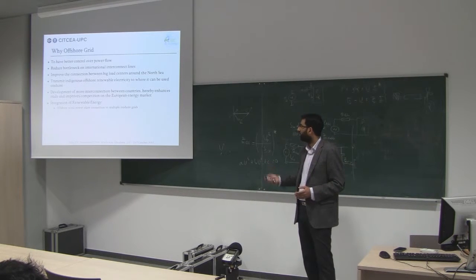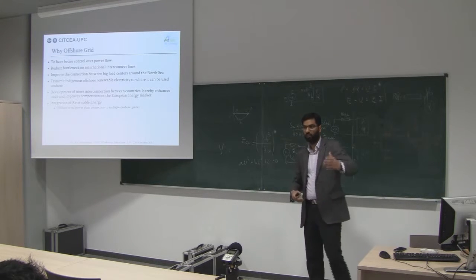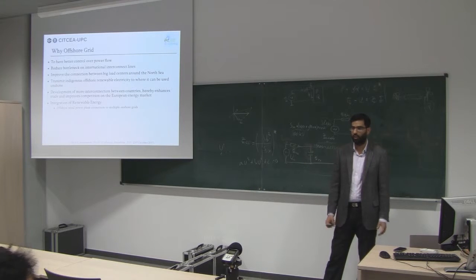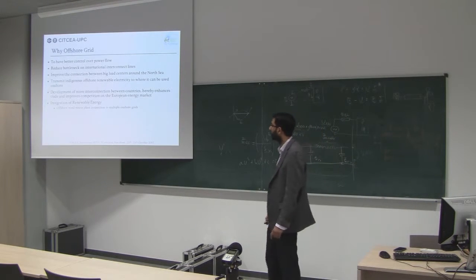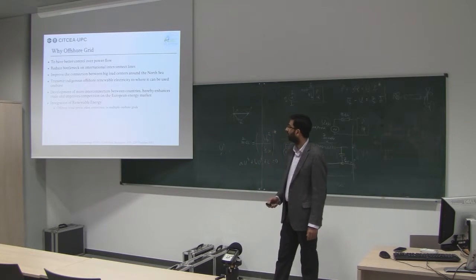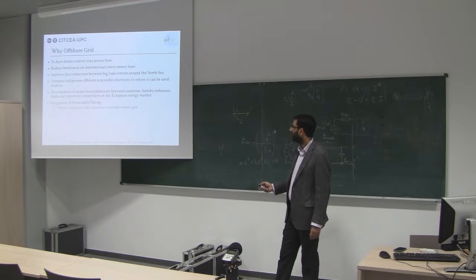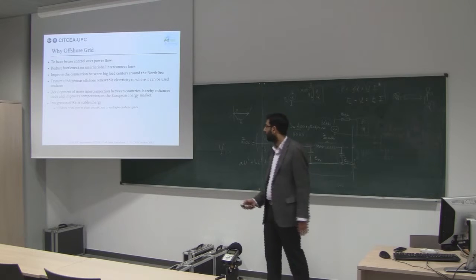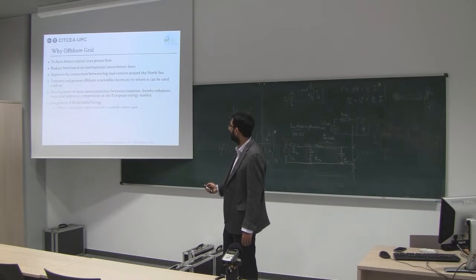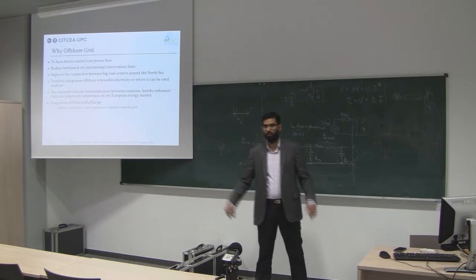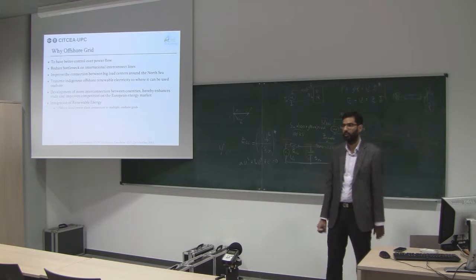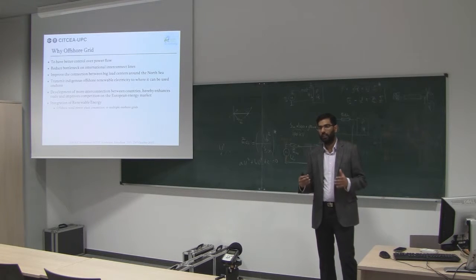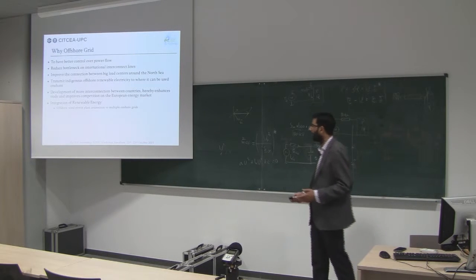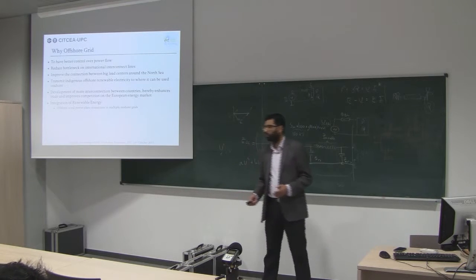The second point is reducing bottlenecks on international interconnectors. If you have a direct connection from a wind farm to another country, you can bypass the existing transmission system, improving the connection between big load centers around the North Sea, and transmitting indigenous offshore renewable electricity to where it can be used. This also supports development of more interconnection between countries, since you have to bypass the sea, where the capacitance effect in cables is greater than for AC lines on land. HVDC doesn't have this capacitive effect, and of course you need it to integrate renewable energy.